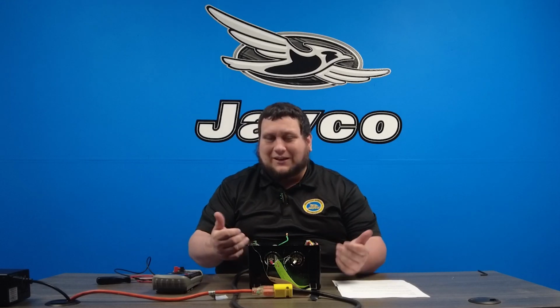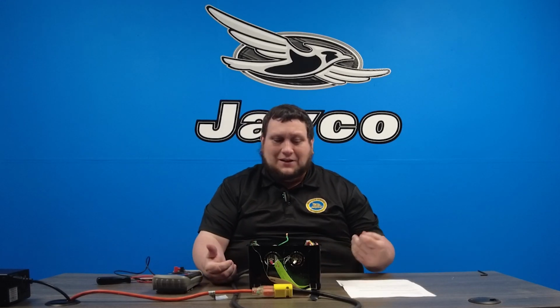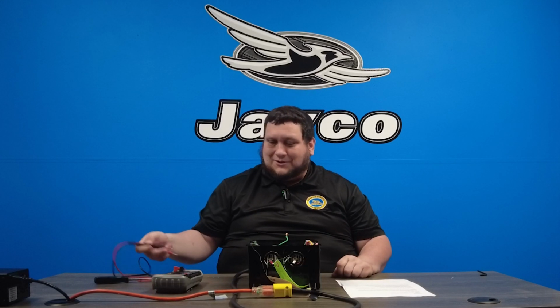If we've tested at the pedestal and made sure we don't have an open ground, and we've tested here at our transfer switch and made sure that we've got good power coming in, and the contactor still fails to transfer over power, at that point we would be looking at replacing the transfer switch.